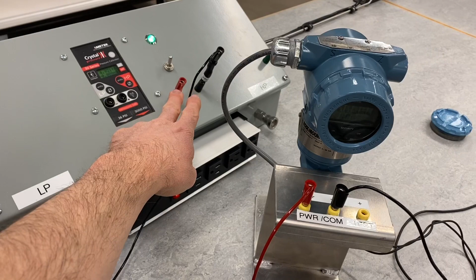We've got it wired up in a normal configuration: 24 volts coming out, a 250 ohm resistor in series, and on the back side our HART modem, the Viator modem, connected to the laptop. The first thing we're going to do is add this device to our AMS database, which is why we have the HART communicator connected.